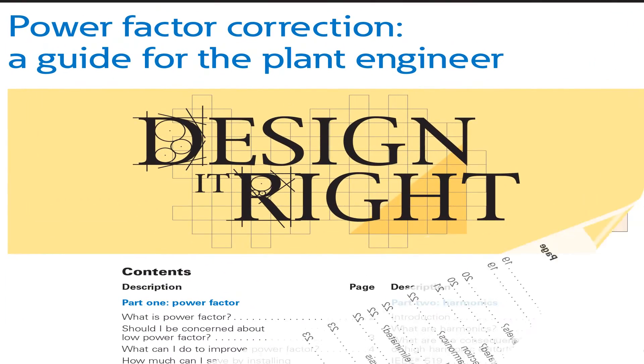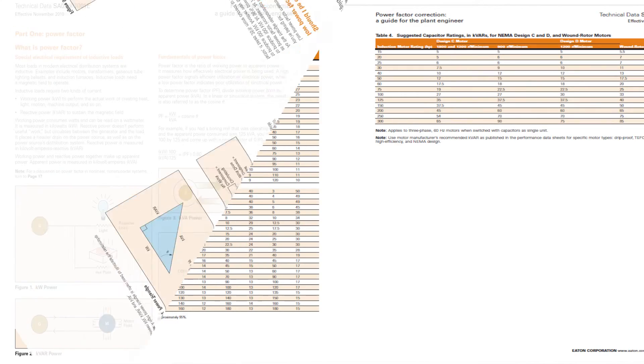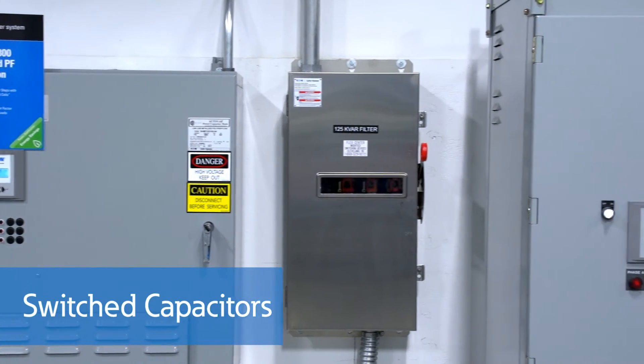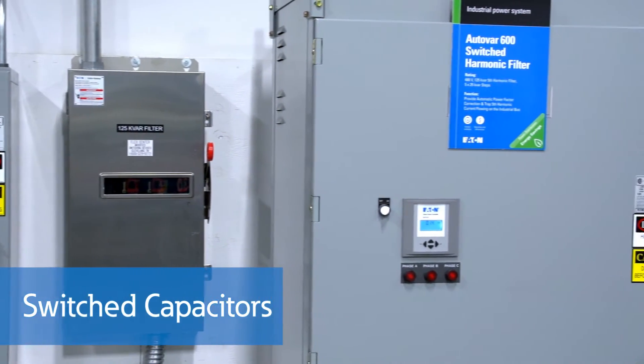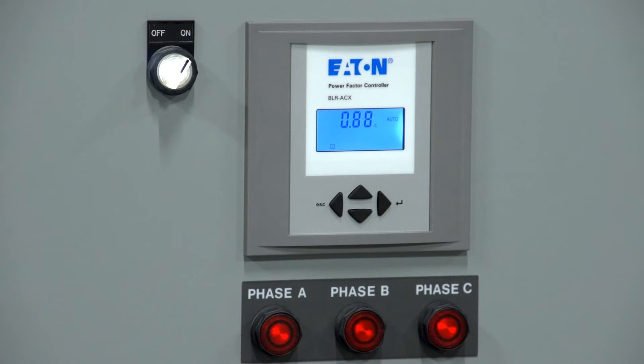Fixed capacitors can be activated with motors to compensate for the reactive power needed to magnetize the windings. There are tables within Eaton's design-it-right guide that can be used to help determine the right size for these capacitors. Fixed capacitors are usually the most economical, but may not be the most appropriate for all situations. Where loads vary, switched capacitors like the Autovar 300 or Autovar 600 use controllers to improve the power factor as loads are switched on and off, by automatically switching groups of capacitors in and out.